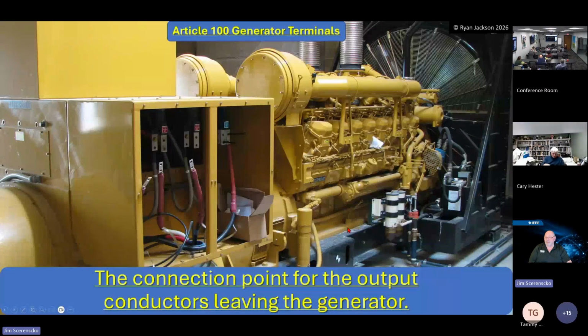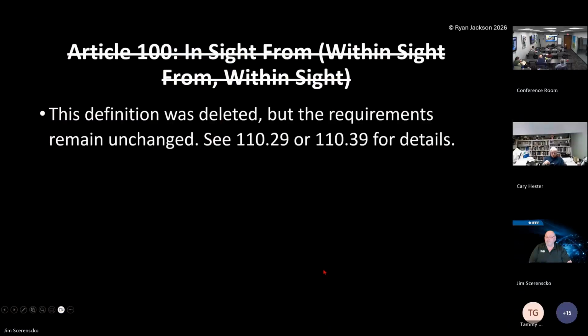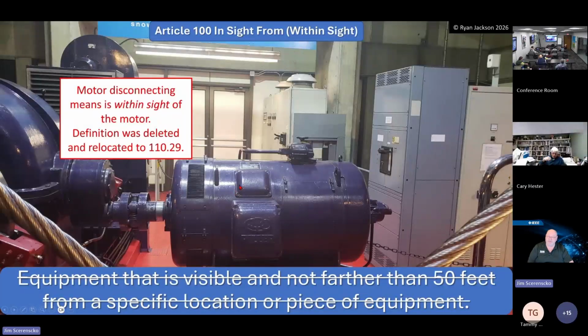Generator terminals, the connection point for the output conductors leaving the generator. The definition was deleted because in 2023 they actually put it in 110.29, so they took it out of the definitions. So it's been a code section, not just a definition, since 2023. And 110.39 is for high voltage. What is in 110.29 says it has to be within sight of, and not more than a travel path of 50 feet, to be considered within sight of.